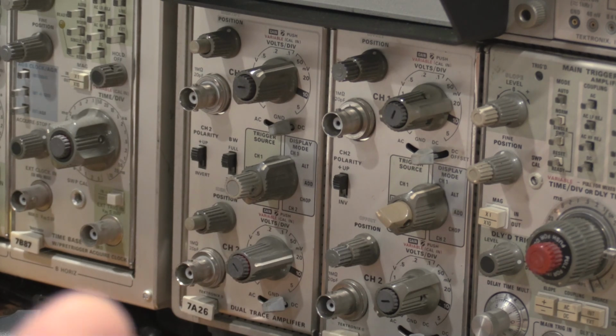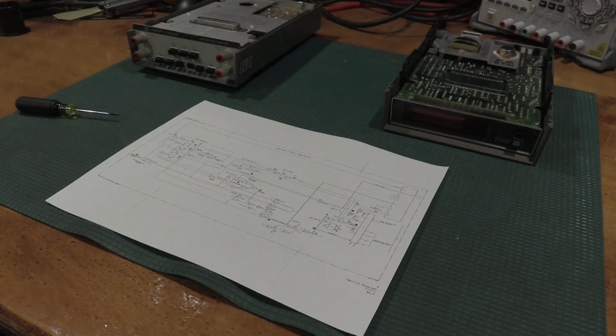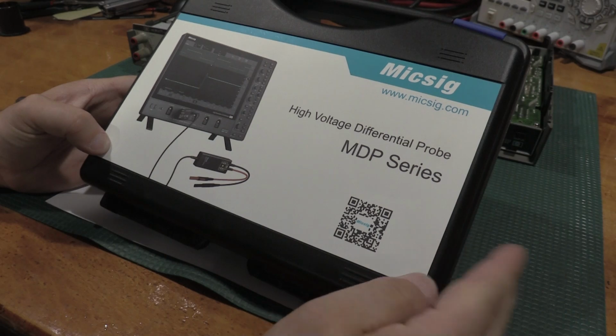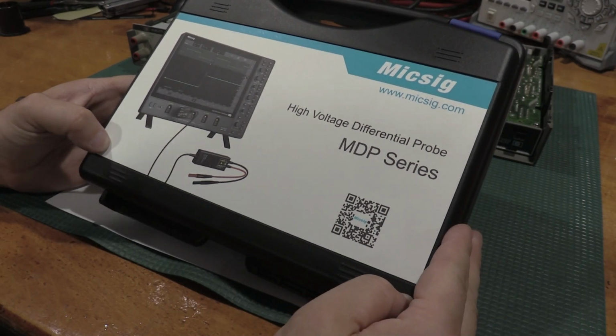So what that had to mean is the noise was present in the power supply. So the signals that I was seeing on the scope were real, but they weren't what I wanted to measure. I was measuring common mode signals of a floating supply with a piece of equipment that was referenced to Earth. So it was throwing the measurements all out of whack, and I needed to take care of something. Enter the Micsig high voltage differential probe.